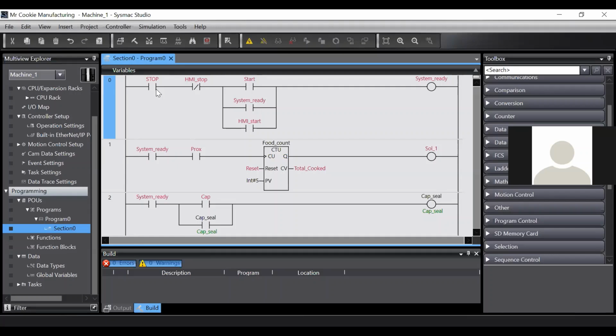Now, can we have an e-stop in here? That is for PLC too, but I can explain that an e-stop is not a stop. And I've talked to you about this. An e-stop would not be located on this program. It would be located on the safety CPU side. Big difference between those two. Are we good?